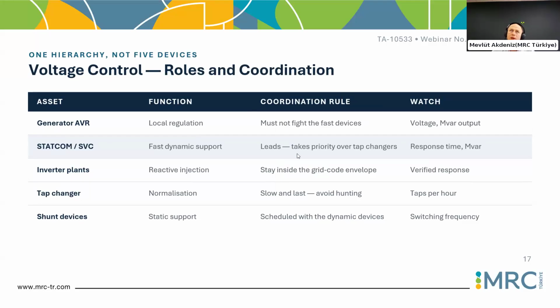And a shunt device could be with a breaker or not. We can also add them to the line itself without breakers. So once the line is energized, the shunt is energized or not. But we can also add it at a breaker if the daily load curve and the generation dispatch curve are very complicated or changing more frequently. We can also add breakers in this shunt device to make it more flexible. But we shouldn't operate the breaker every hour in a day, as they have a limited life cycle. So maybe a couple of times in a day is more preferable.